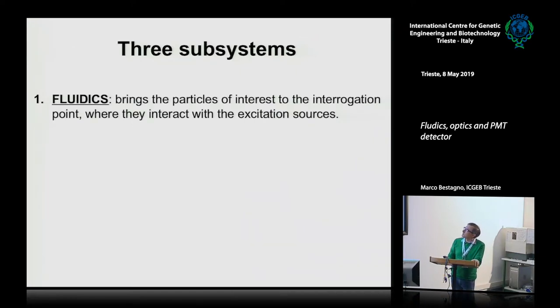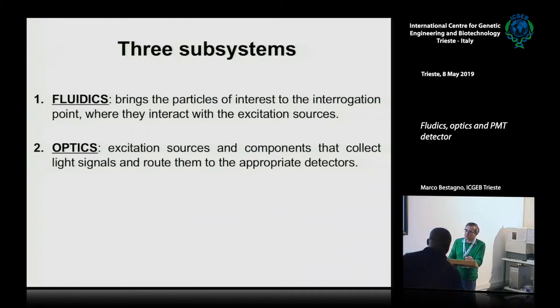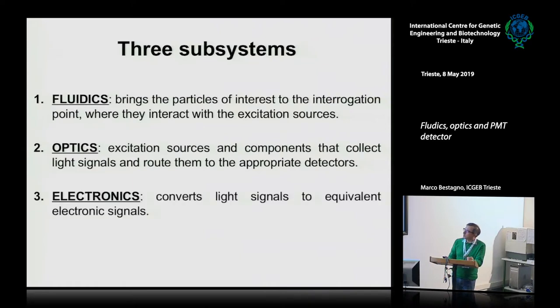The fluidics subsystem brings the particles of interest to the interrogation point where they interact with the excitation source. The optics subsystem consists of the excitation sources — basically lasers — and the components that collect and route light signals to the appropriate detectors: mirrors, lenses, filters, and optical fibers. The electronics subsystem includes all devices that convert the light signal to equivalent electronic signals — photodetectors, photomultipliers — and then the software that elaborates these data.